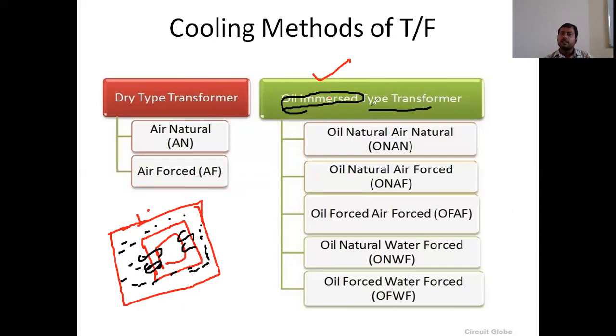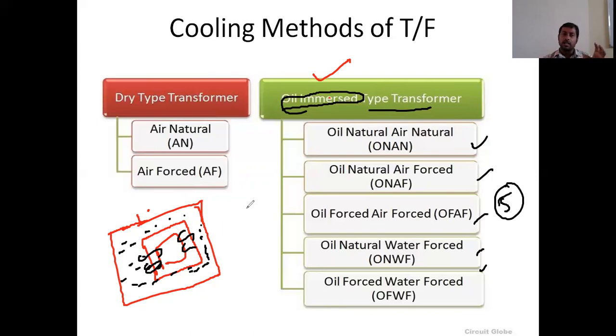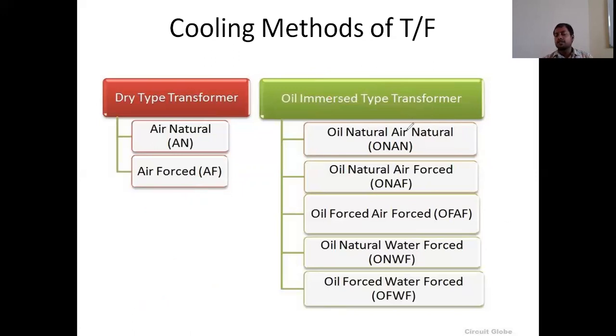All five methods — one, two, three, four, five — are based on oil immersed type, meaning the core and winding are placed inside oil, and the oil is placed in the tank of the transformer. Based on capacity, the oil immersed type is classified. The first is ONAN — Oil Natural, Air Natural. In oil natural air natural, naturally oil flows to the radiators and back.